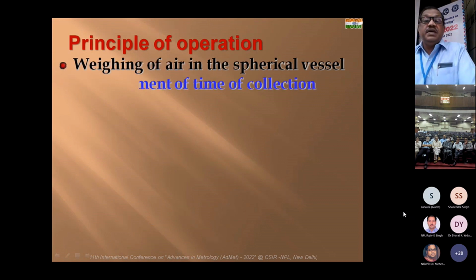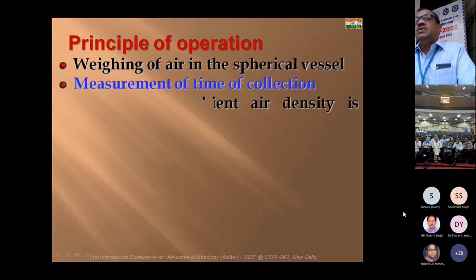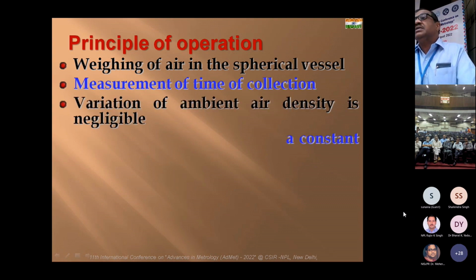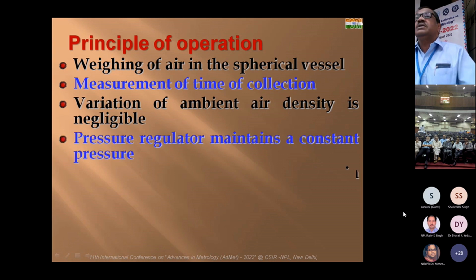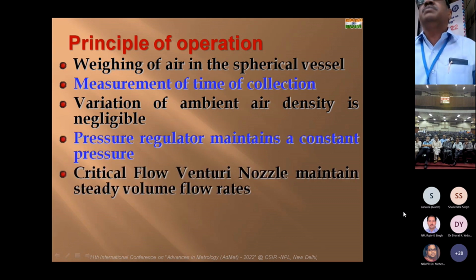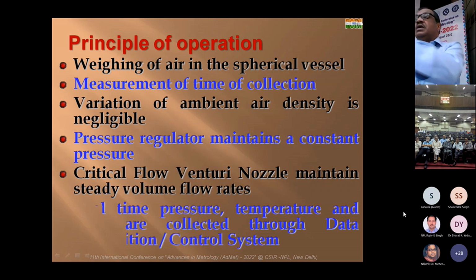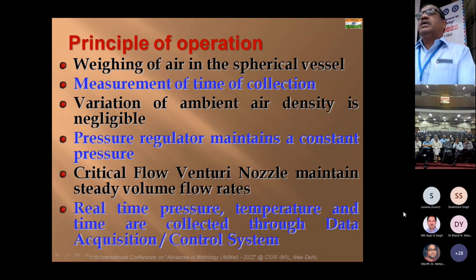The principle of operation is weighing of air in a spherical vessel. For liquid applications, it is very easy to weigh the liquid, because with any container you tare the initial mass, collect some of the liquid, take the final mass, and time it with either a stopwatch or a counter, whatever it is. You easily get the result and can compare mass to mass or flow rate to flow rate. It is quite easy, but it is somewhat complex for gas because of the compressibility nature, and the measurement of time.